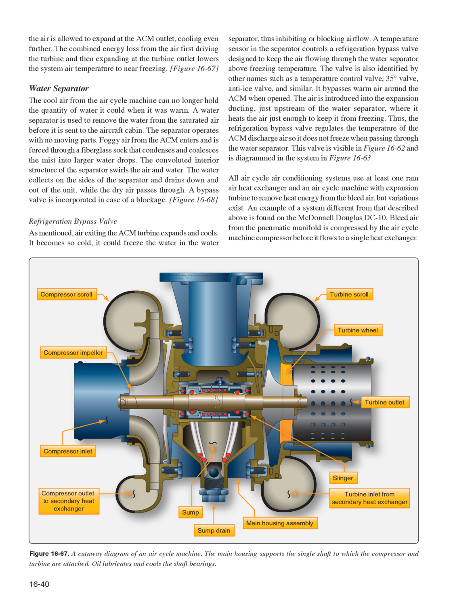Foggy air from the ACM enters and is forced through a fiberglass sock that condenses and coalesces the mist into larger water drops. The convoluted interior structure of the separator swirls the air and water. The water collects on the sides of the separator and drains down and out of the unit, while the dry air passes through. A bypass valve is incorporated in case of a blockage.